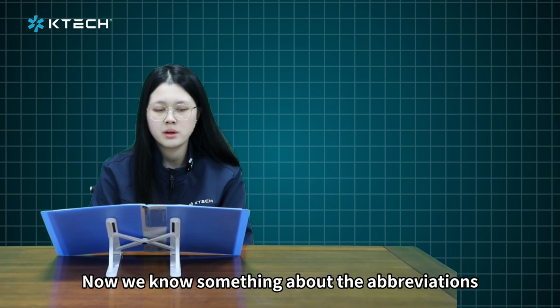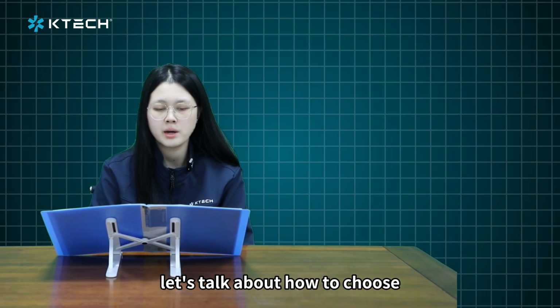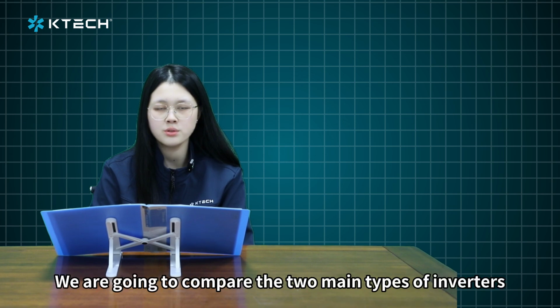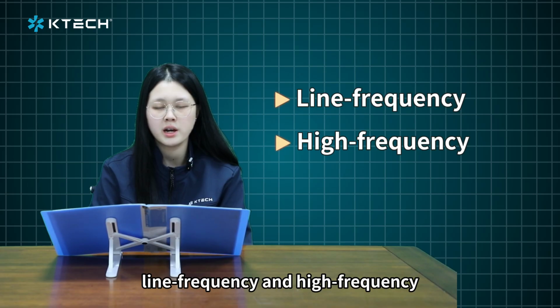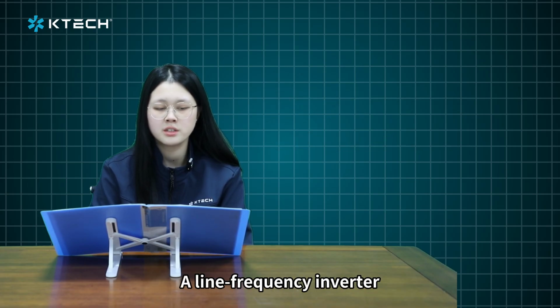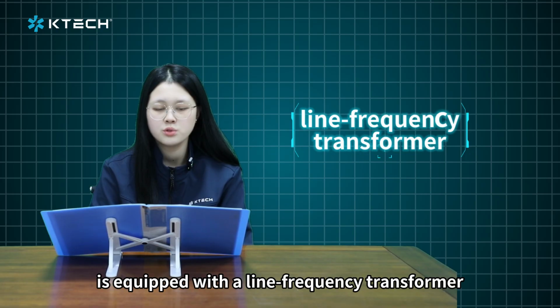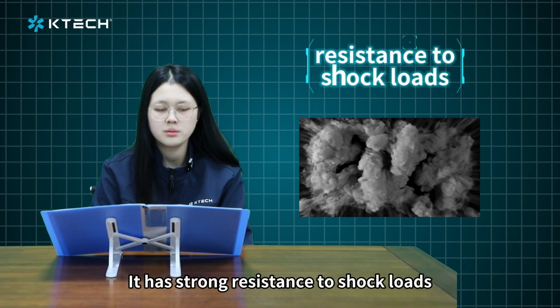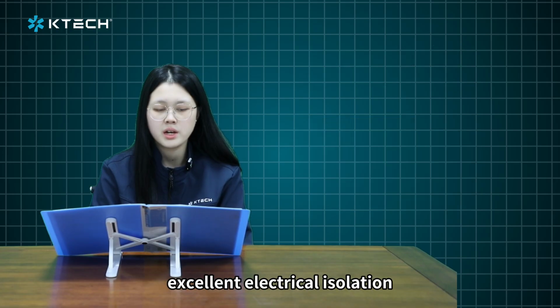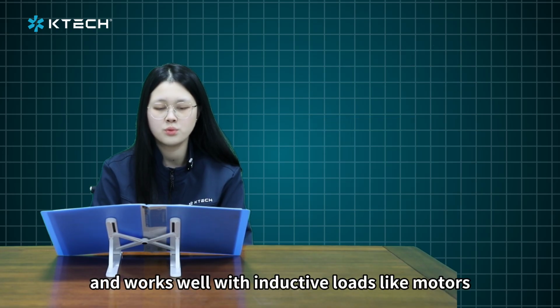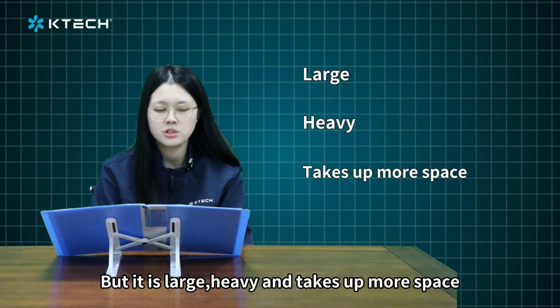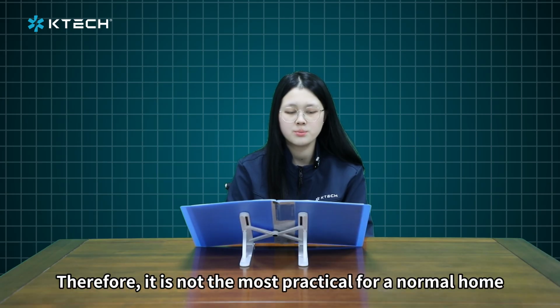Now we know something about the abbreviations. Let's talk about how to choose. We are going to compare the two main types of inverters, line frequency and high frequency. Line frequency inverter is equipped with a transformer. It has strong resistance to shock loads, excellent electrical isolation, and works well with inductive loads like motors. But it is large, heavy, and takes up more space. Therefore, it is not the most practical choice for a normal home.